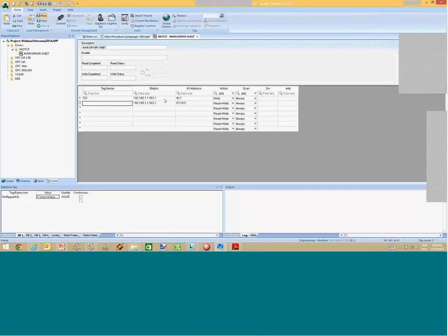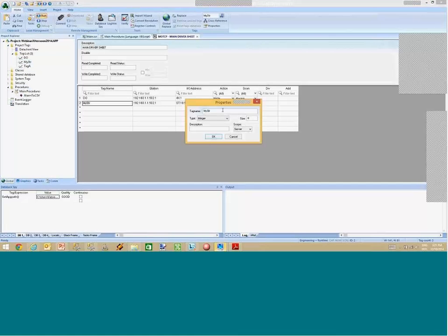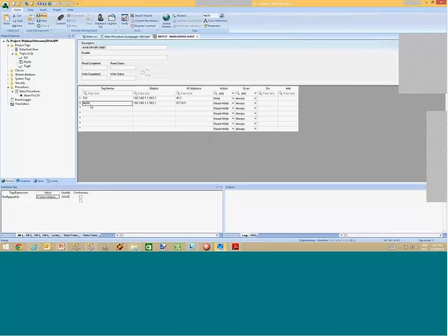So I could have a tag here, MyStr. Create this tag as a string tag. And by changing the value of this tag, I write this value as a string. Actually, each ASCII character is one byte, starting on holding register 10 and the 5 subsequent bytes, Modbus holding registers, and I write this string to the device using the Modbus driver. That's one way of answering the question if you want to write a string to the actual device.